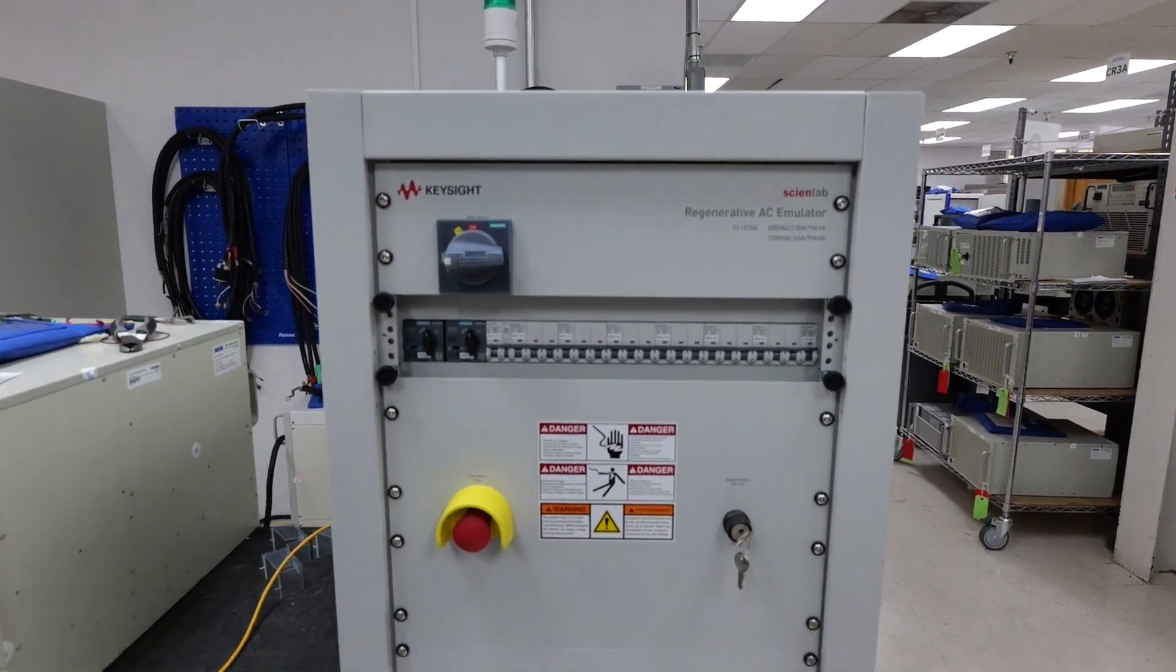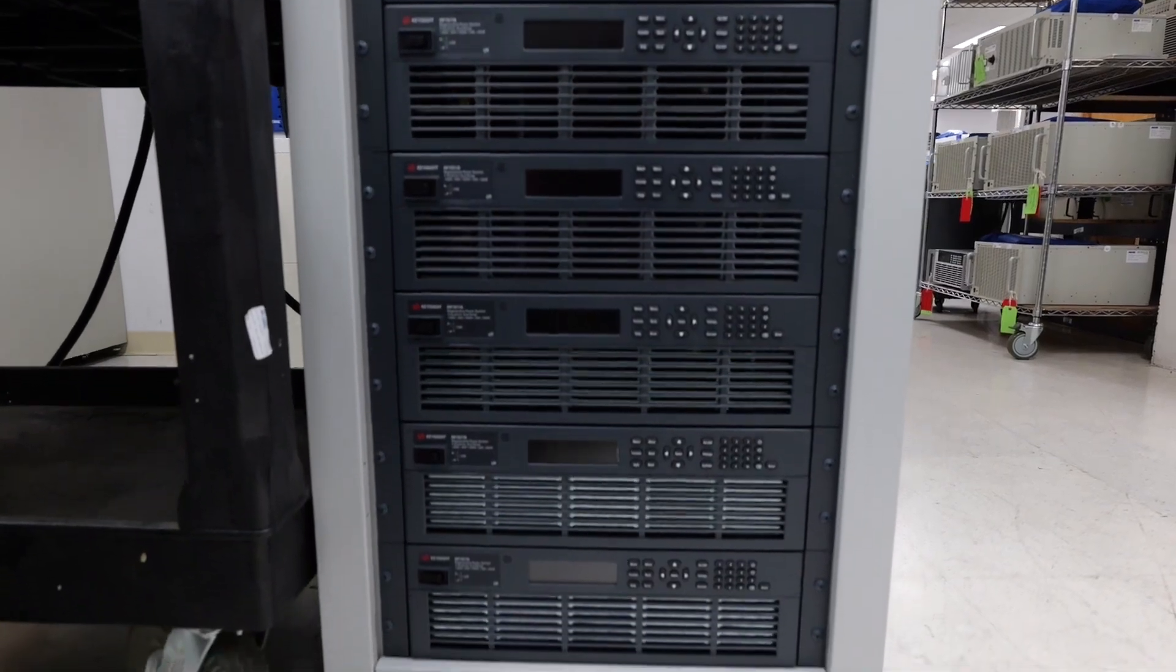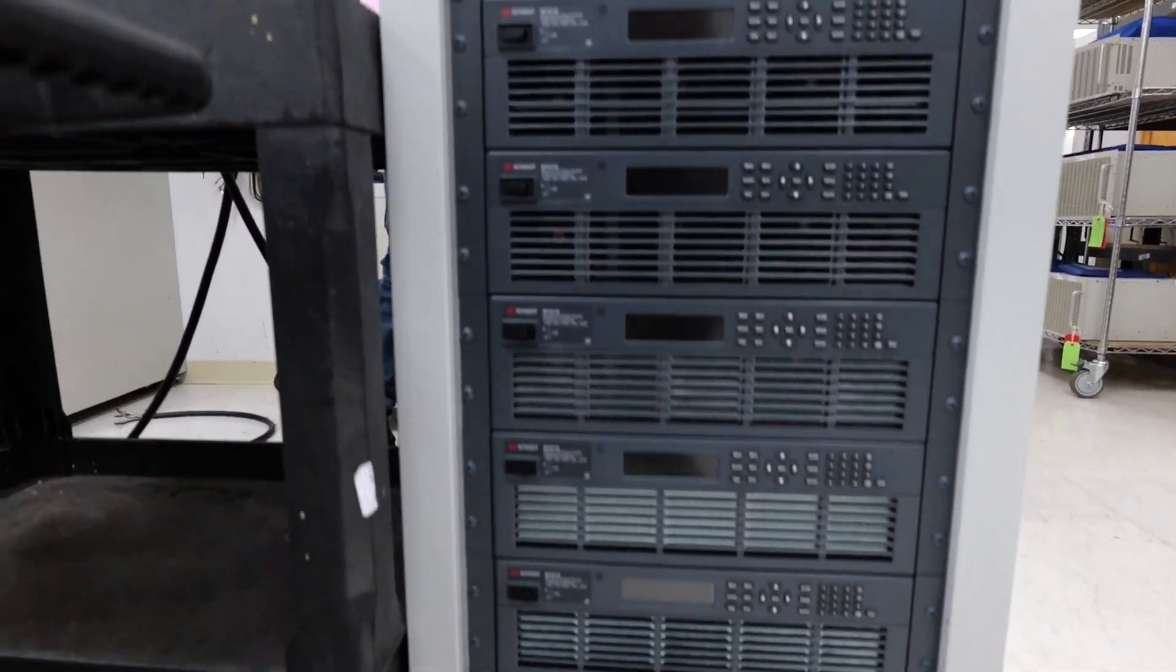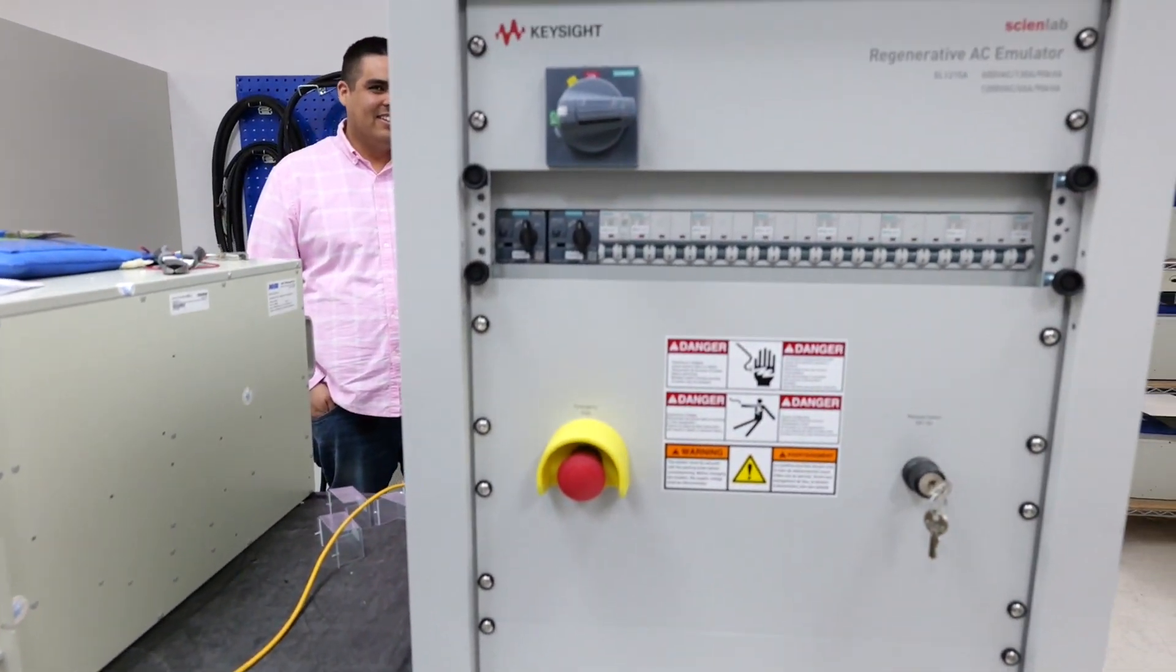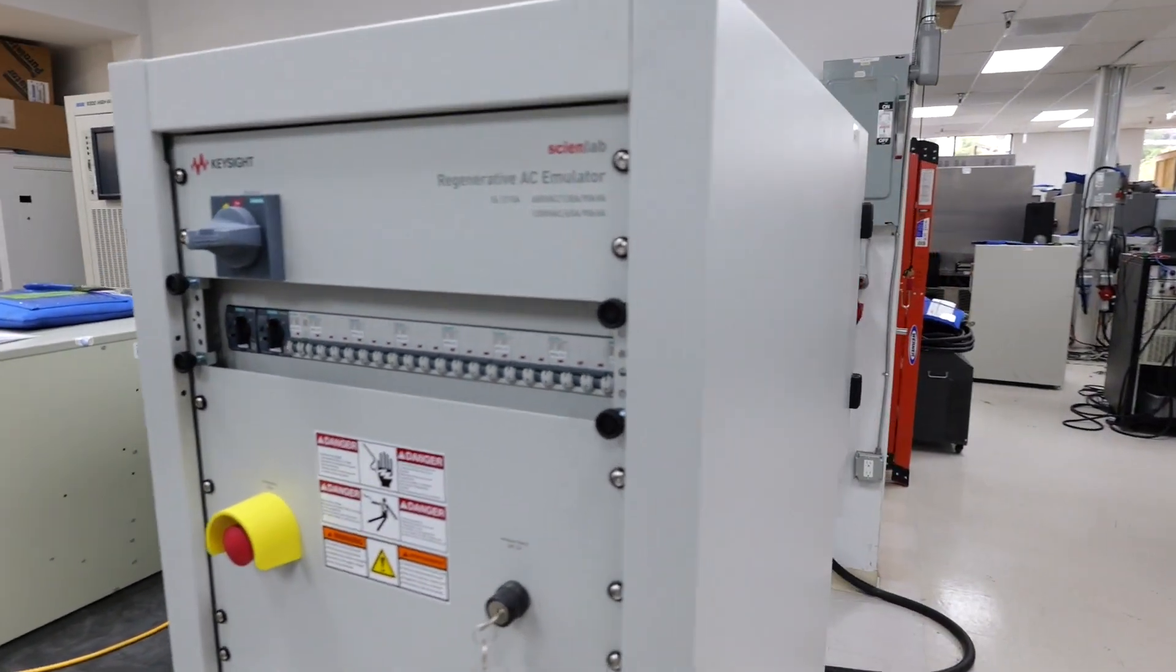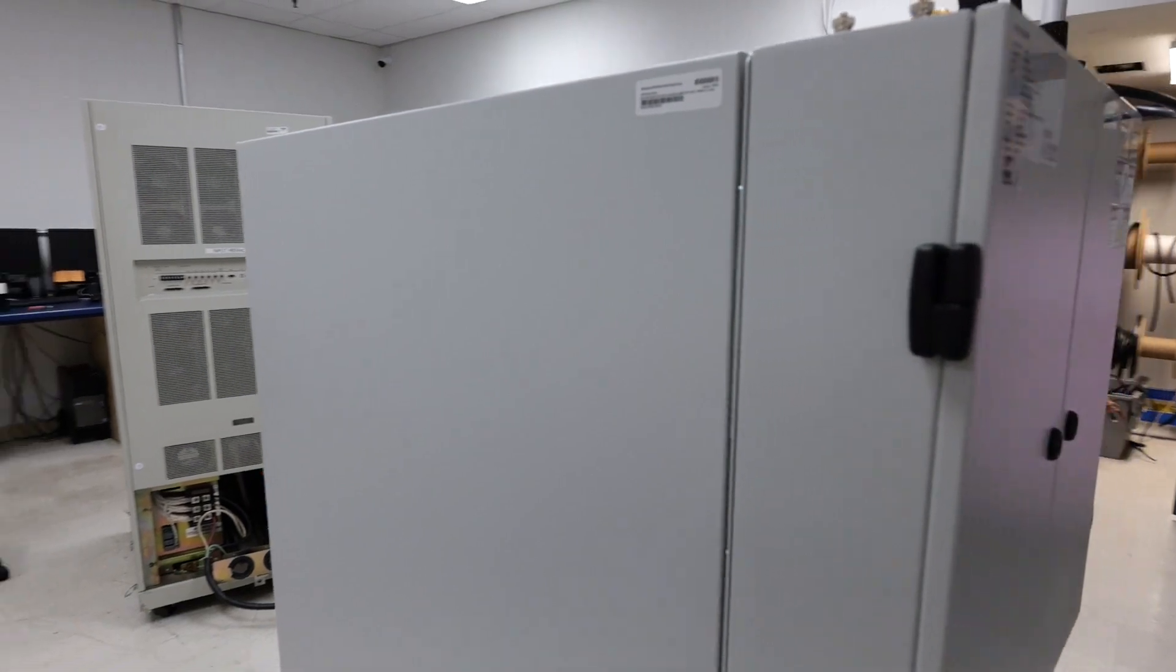The Keysight SL1215A is both an AC and DC source and load. It's capable of up to 1,200 volts AC at 90 kVA and up to 1,000 volts DC at 120 kilowatts.